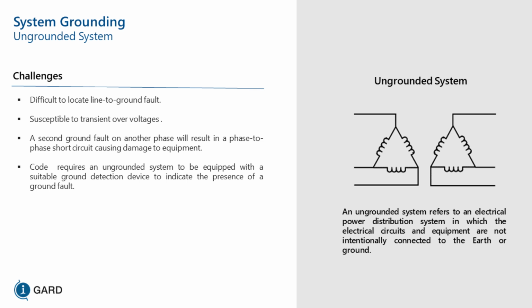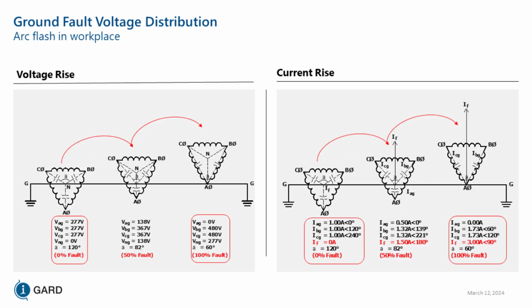So you can't find the ground fault, and the code says that you need indicating lights. So lights are connected from phase to ground. When you get a ground fault, one of those phase indicating lights extinguishes, and the other two get brighter. So that's how you can tell if you have a ground fault. The difference between a burnt out light bulb and a ground fault is minimal because the other two are always going to look brighter.